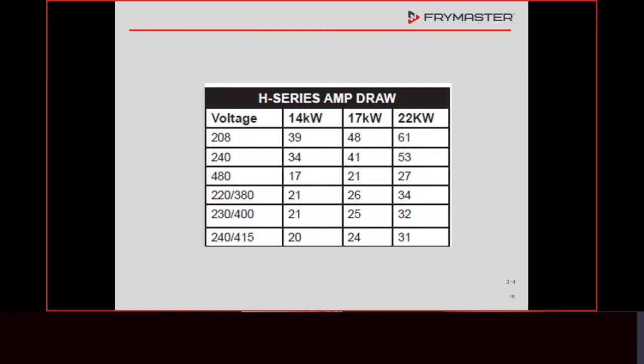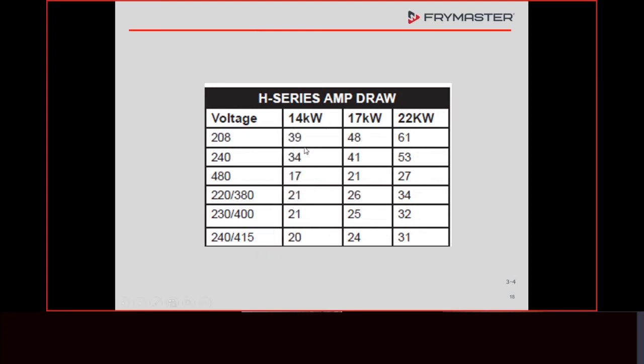I've worked with electricians before that were retrofitting stores for electric. You can do it at the breaker box. I'm not suggesting you have to do that. If you can't get a 3-phase amp draw actually on the terminal block, you can just do an amp draw on each one of the wires, and make sure when it's calling for heat, each one has an amp draw. Like on this fryer here, you would have about 11 amps per wire. I just know that because I've done enough of them. And then when it stops calling for heat, make sure everything goes back to 0.